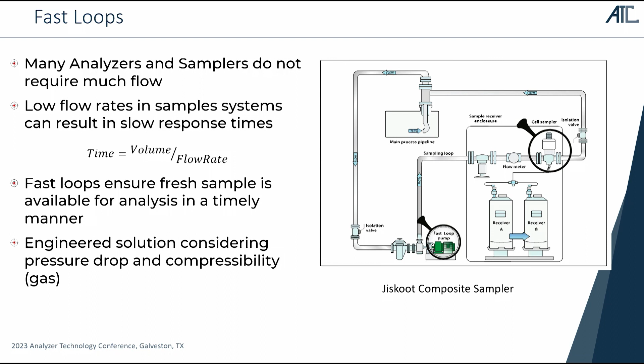There's a lot of issues and common problems that come up when we consider how to implement a fast loop at our facility. One common one is we only have one sample point to measure from, but no low pressure return point. So we have to figure out where that low pressure return is going to go. If we don't have a low pressure process point, we can't return to the same pressure, so maybe we need a pump. And if we're going to return to a low pressure place like the flare header, we may be concerned about the volumes we're going to put there.